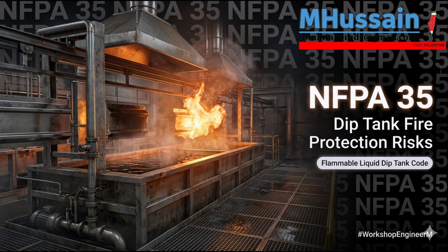It really does. And to prove that the piping is flawless before a single drop of chemical is introduced, the contractors must perform hydrostatic testing. The standard requires all piping to be hydrostatically tested to not less than 1.5 times the expected working pressure. And it has to hold that massive overpressure for a minimum of 30 minutes without a single drop leaking. And the key word there is hydrostatic, meaning using water to test the pipes, not pressurized air. Right. The physics of the testing medium is literally life or death here. Water is an incompressible fluid. If you pump a pipe full of water to 1.5 times its rating and the pipe fails or a weld cracks, the water just squirts out. The pressure drops instantly to zero. It's wet, but it's safe.